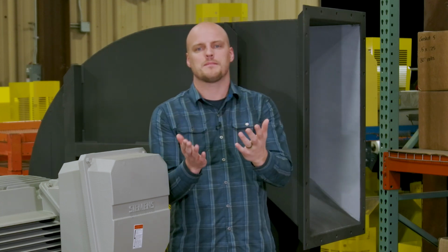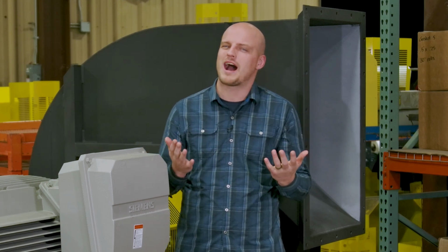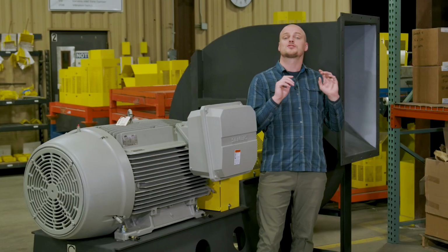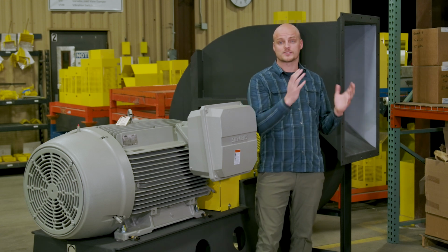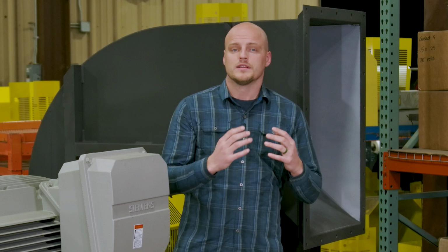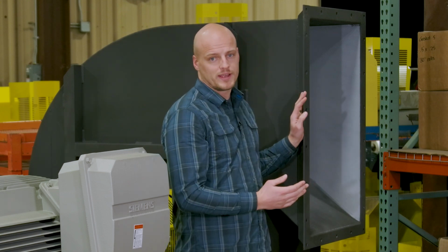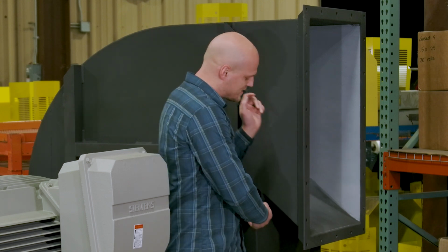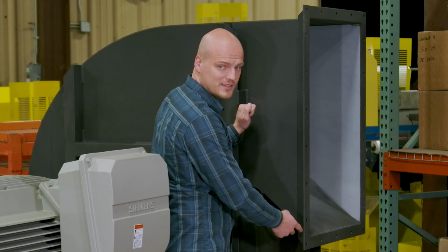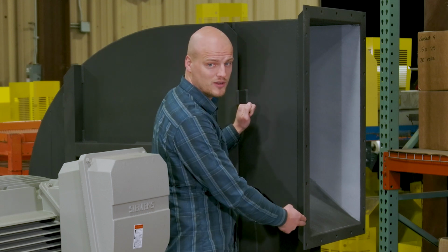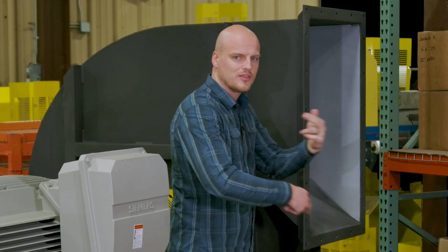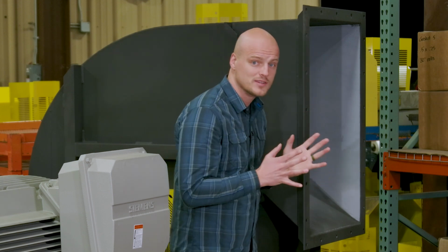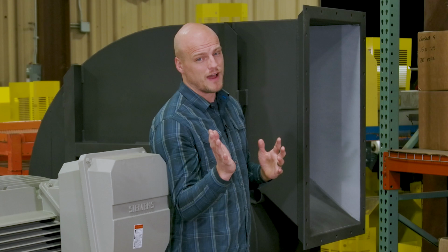So how will that impact performance of your fan in your system? It depends on how high the velocity is. So you want to give your gas a path for it to normalize off the outlet of the fan. So you can do that in a number of ways. First of all, you can continue along this natural évasé that we see right here built into the outlet of this fan by putting another évasé on the outlet, and that will allow the air to continue to develop into a normalized flow a bit faster.